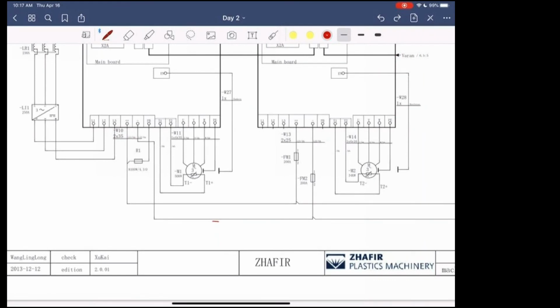And down here, you have a brake resistor. This brake resistor, what that does is, because there are large capacitors on these drives, if you didn't have a brake resistor, a place for them to dissipate, when you disconnect the power off the drives, they would still be live. Also, this helps stop the motors. So it's used for various things, but the most important one is to dissipate the energy out of the drives. It also helps the motor stop exactly where it's supposed to stop, but that's a different thing. We won't discuss that.